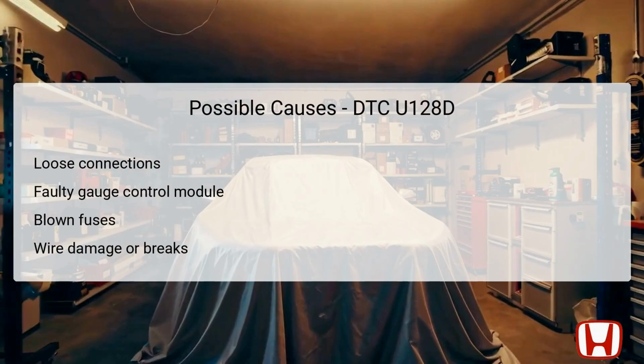Loose connections are a common problem, which may result from wear and tear or improper installation practices. When connections become loose, each module may not receive the necessary signals or power it requires, leading to communication failure. A faulty gauge control module, which could be due to wear or manufacturing defects, may also directly hinder communication. Another possible cause is a blown fuse, which may interrupt the electrical flow necessary for proper functionality. Finally, damaged or broken wiring can prevent the transmission of signals between these two key modules. Each potential failure point requires careful examination during the troubleshooting process to isolate the exact cause of the communication fault.